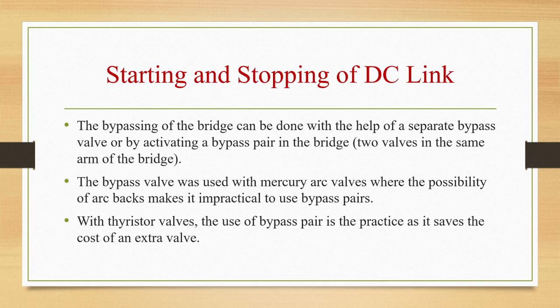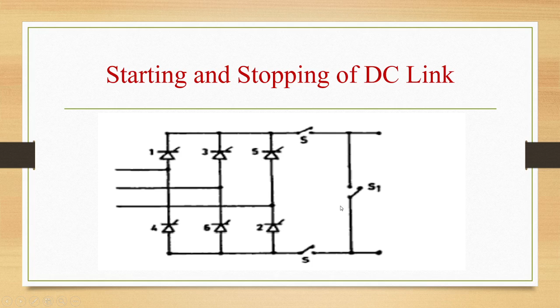The process of de-energization of a bridge is explained with reference to this figure, where we can see six thyristors: the odd numbers 1, 3, 5 and the even numbers 4, 6, 2. These are the switches S and S1. Valves 2 and 3 are assumed to be conducting initially when the blocking command is given. With the selection of bypass pair 1 and 4, commutation from valve 2 to 4 is in the usual manner, but the commutation from valve 3 to valve 5 will be prevented.